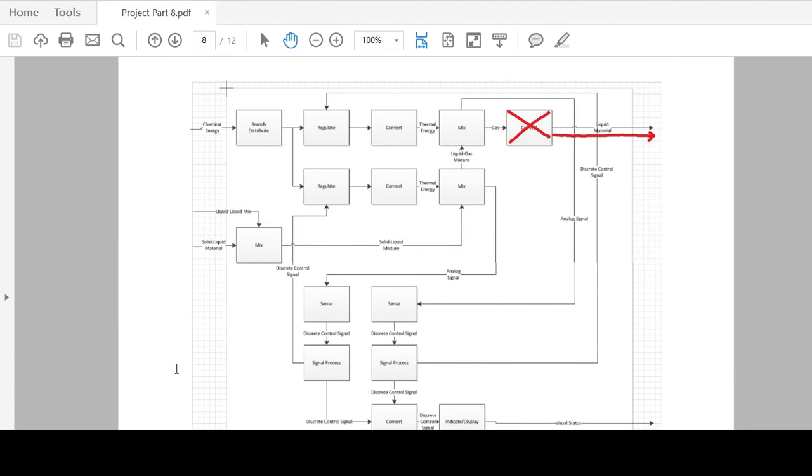Next, looking at the failure of the condenser, which essentially cools down the incinerated fluid. If that fails, the fail propagates throughout the system, and what this basically means in this case is that steam is dumped into the sewers instead of liquid. This isn't ideal, but it doesn't actually affect the effectiveness of the system, as all microbes are still killed.